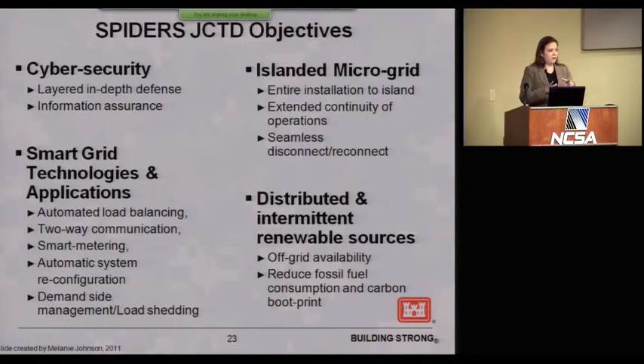So with our existing diesels and fuel tanks, we could run for 3 days. With a microgrid, we need to be able to run for longer, and have seamless disconnect and reconnect from the grid. Although there are other challenges to that, backfeeding the utility is never something utilities are a fan of. So most of the first two demonstrations of SPIDERS will actually be break before make, as far as the microgrid goes.